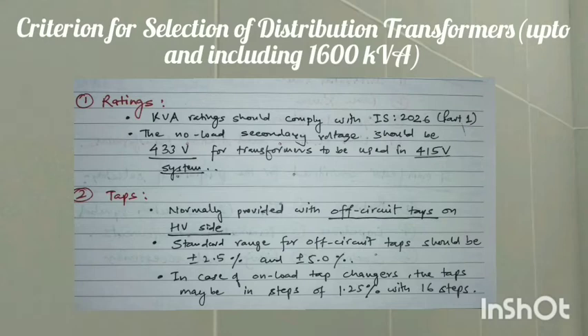Second, taps or tapping. Transformers are normally provided with off-circuit taps on the HV side. The standard range of off-circuit taps should be plus or minus 2.5 percent and 5 percent. In case of on-load tap changers, the tap may be in steps of 1.25 percent with 16 steps.